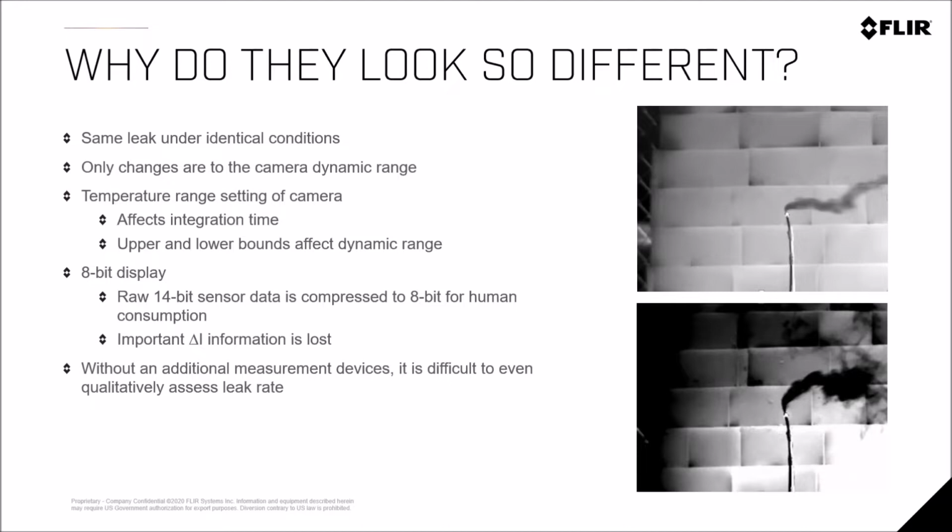Now, we can't use the various temperature ranges in the manual with the camera. So when you're utilizing a QOGI solution, I believe that the camera will lock into the auto plume, and that auto plume is the way that the QL320 calculates that delta I, or that change in intensity from one pixel to the next, and how much that intensity changes compared to the background that may not be getting into the detector.